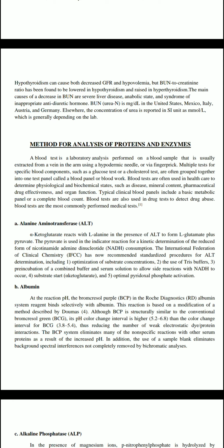Now the second one is albumin. At the reaction pH, the bromocresol purple (BCP) in the Roche Diagnostics (RD) albumin system reagent binds selectively with albumin. This reaction is based on a modification of a method described by Doumas.